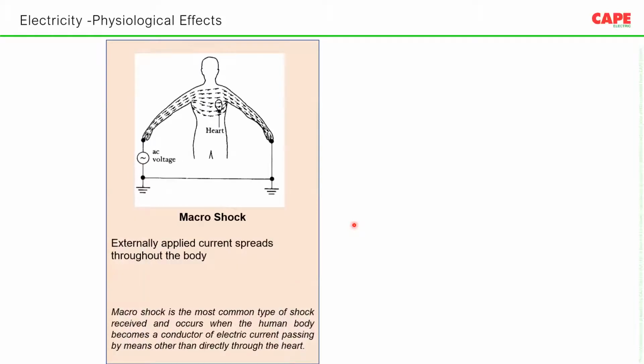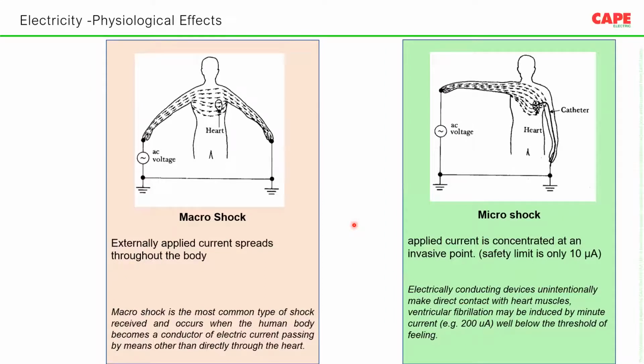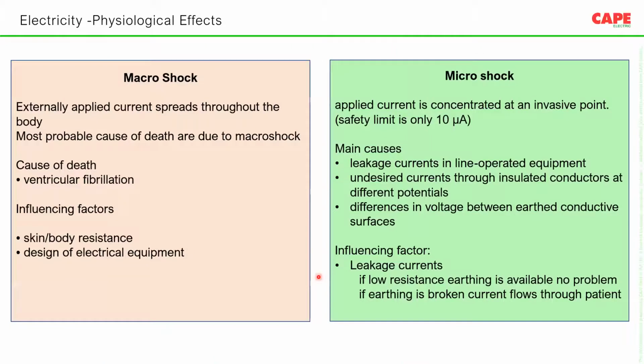What is recommended, or what is the problem? The patient has a lot of electromedical equipment connected to his body. Even a small current flow through the body, depending upon how he is placed, how he is sleeping, or how he is on the bed, there are chances of micro shock and macro shock. Mostly these shocks, depending upon the situation, are fatal to the patient. This is the reason protective equipotential bonding, especially supplementary equipotential bonding, is needed: the entire electrical appliances in the patient environment shall be interconnected. This is what the new standard IS 17512 explains.